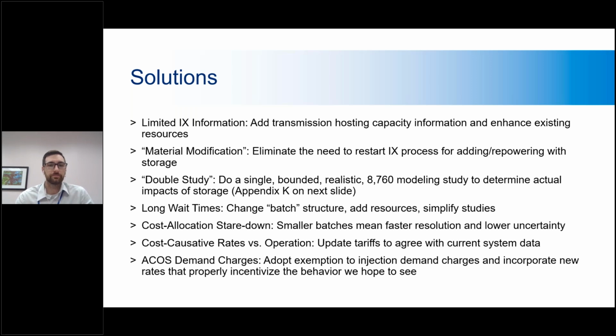On the material modification issue, I think the easiest thing to do is just eliminate it. Saying energy storage is a material modification of your site, forcing it through its own interconnection process just to add storage to an existing site, is very difficult and expensive. I don't know of any other ISOs that require this, and eliminating it would avoid restarting the interconnection process, allowing a lot of storage to be installed quickly at existing sites that might have somewhere between 20 and 100 megawatts of existing headroom.